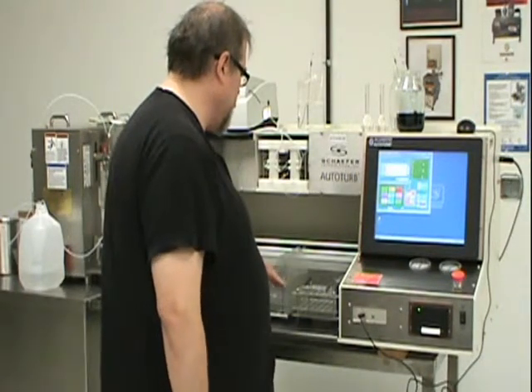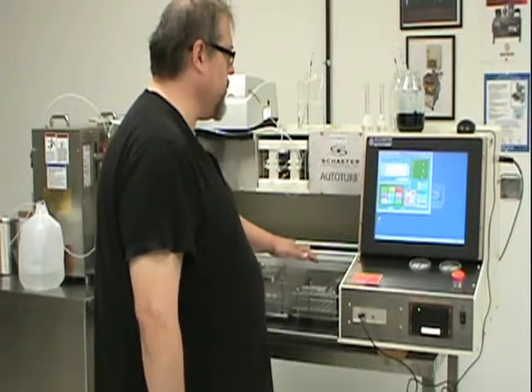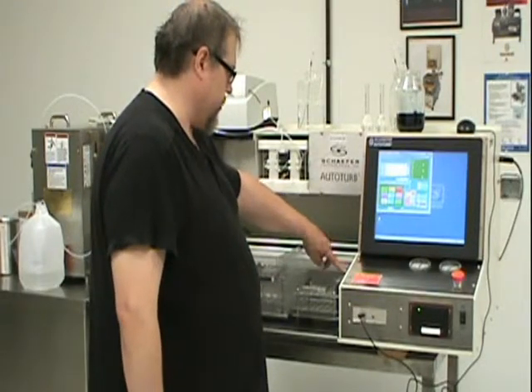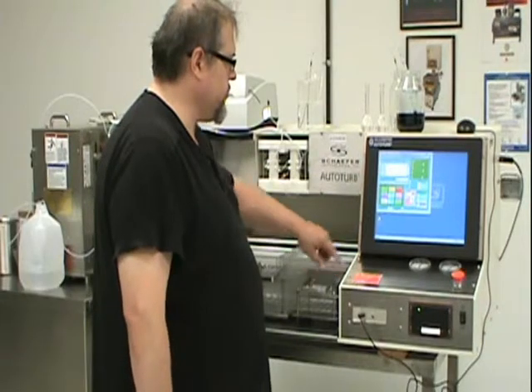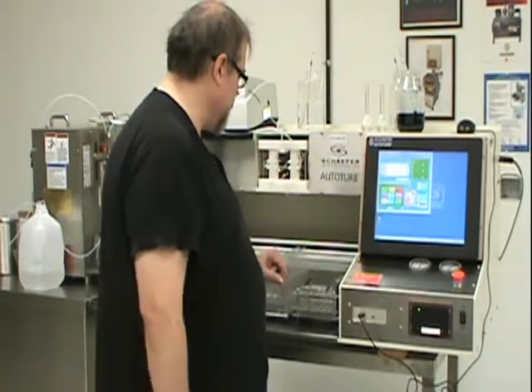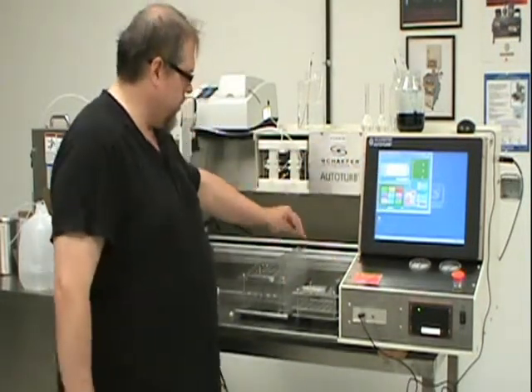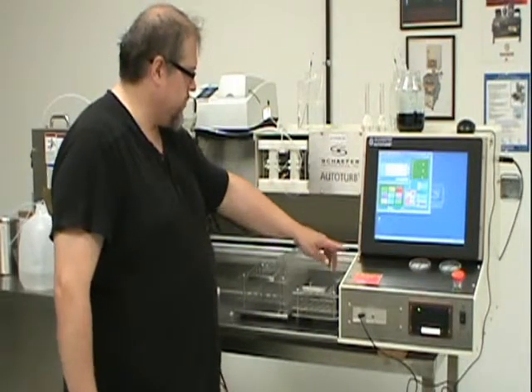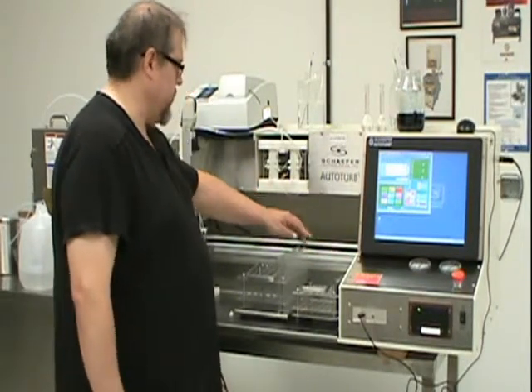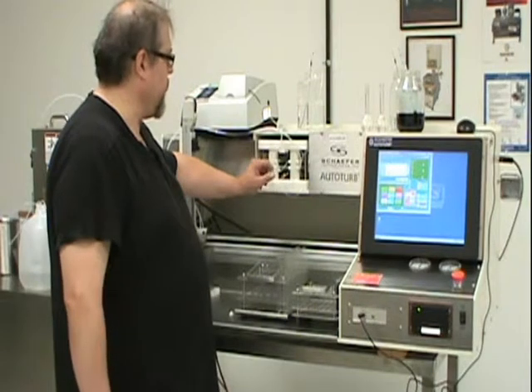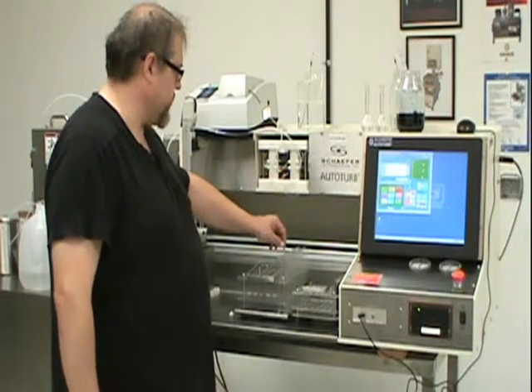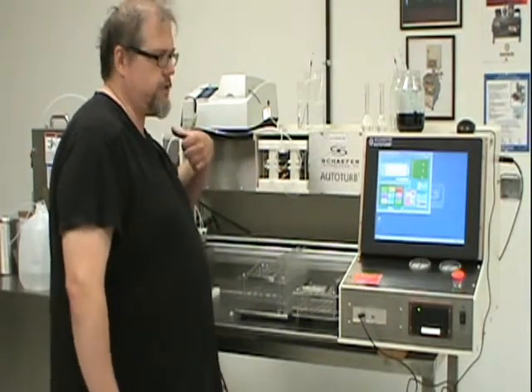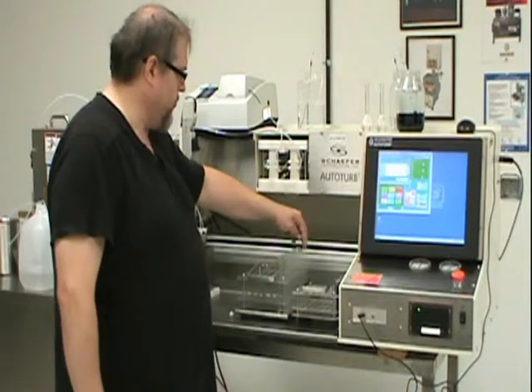The next step we'll do is an alternate mode test for diluting, which will draw fluid from each of these 5 test tubes because we're going to tell it 5 samples. It will dispense 4 dispensings of each one of these tubes into the rack. We draw fluid in here, we fill up the 0.1 and 0.15 milliliter loops, and then when we dispense them, we push 10 mils of fluid with the contents of the loop into the tube.